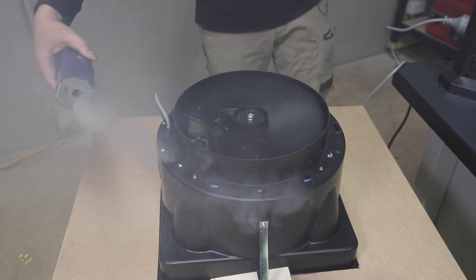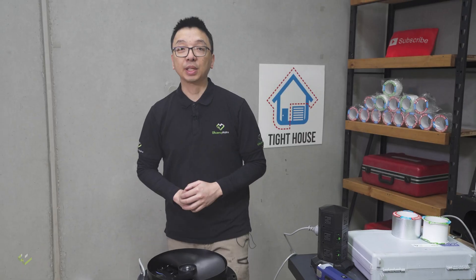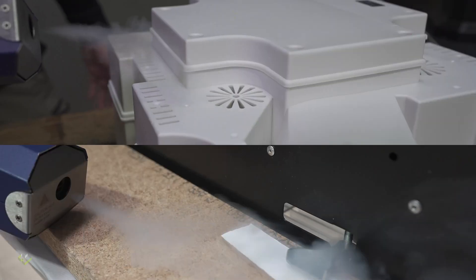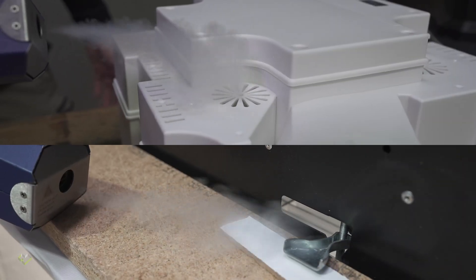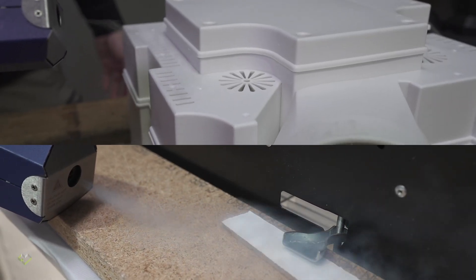So if I try to run this fan and exhaust and if I pump smoke in the roof area it will not be sucking back in the room because the whole unit is in negative pressure.